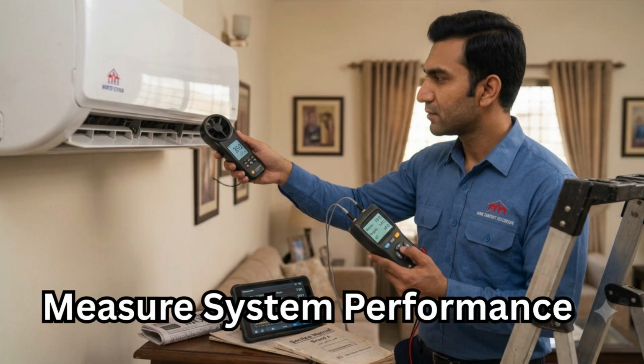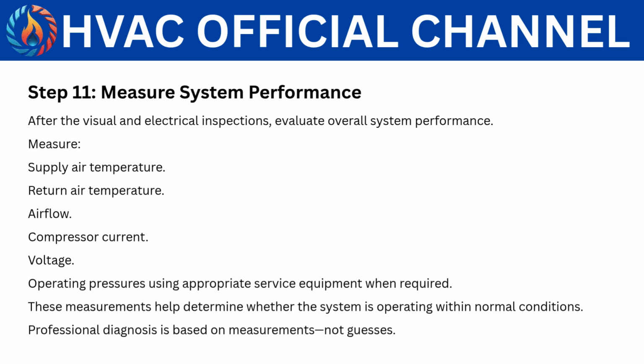Step 11. Measure system performance. After the visual and electrical inspections, evaluate overall system performance. Measure supply air temperature, return air temperature, airflow, compressor current, voltage, and operating pressures using appropriate service equipment when required. These measurements help determine whether the system is operating within normal conditions. Professional diagnosis is based on measurements, not guesses.